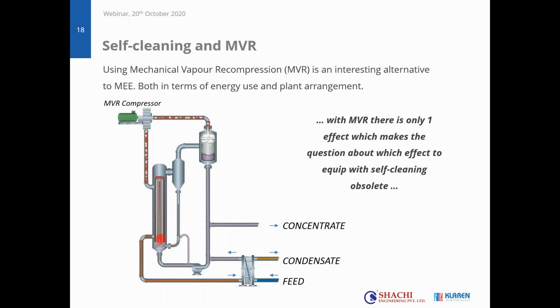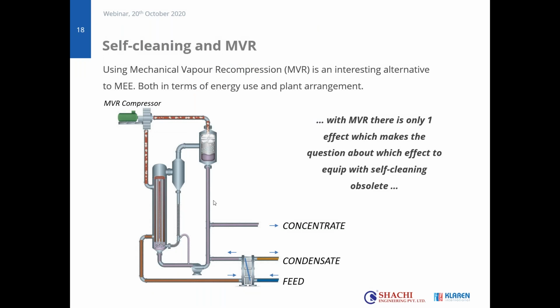So the vapor is condensed. In fact, this is also a condenser. And by this condensation, this liquid is heated, it flashes, goes back to the recirculation pump, and then is heated again. And this continues. So you condense the vapor that is generated, and this is fully condensed. So there's no vapor left anymore. That also means that there is no condenser needed anymore. So no cooling tower also to create cooling water for the condenser. So in that sense, a lot of the elements are no longer required that you would require in a multi-effect evaporator. So this is in fact the principle behind the MVR unit.